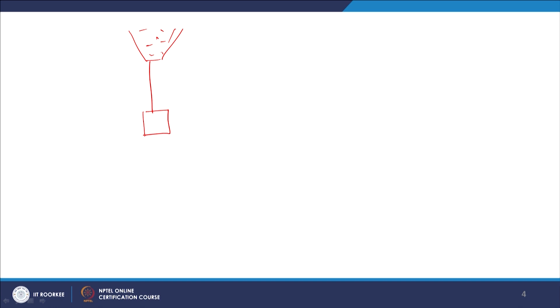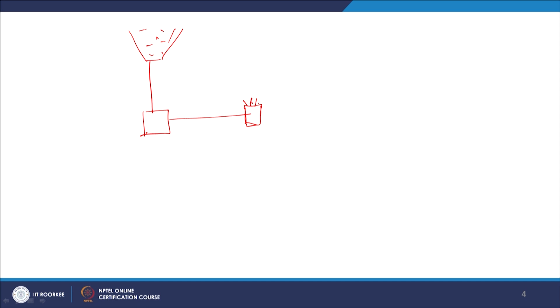In central type of system, the feeder is the same, I mean the raw coal comes from here. Let us say this is a feeder, there is only one feeder. It goes to the pulverizer and there can be a number of pulverizers. I am showing only one, there can be 3 or 4 large size pulverizers. The outlet of the pulverizer is connected to a cyclone separator.